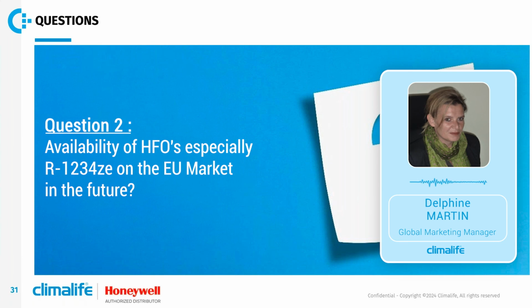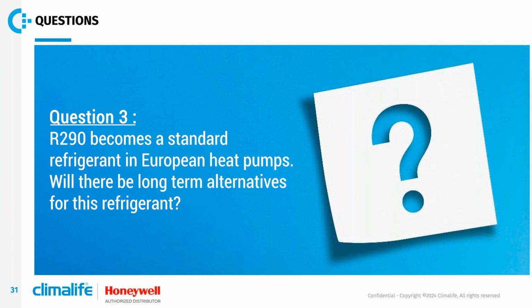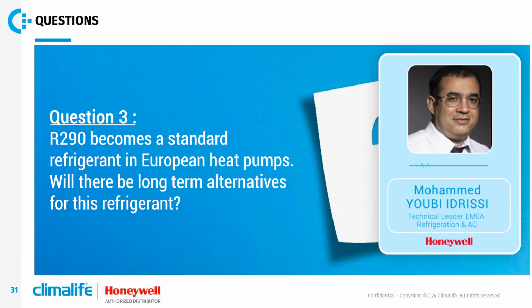Okay, thank you, Pierre-Emmanuel. Another one concerning propane. R290 becomes a standard refrigerant in European heat pumps. Will there be long-term alternatives for these refrigerants? Yeah, I can take this question. In fact, you say that propane is a standard solution for heat pumps. I don't agree totally with that. It depends on the type of heat pump. It can be true for water-to-water heat pumps, maybe water-to-air heat pumps, but absolutely not for air-to-air heat pumps.